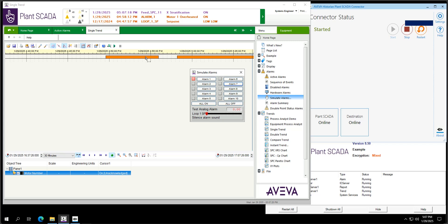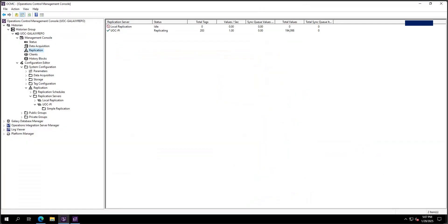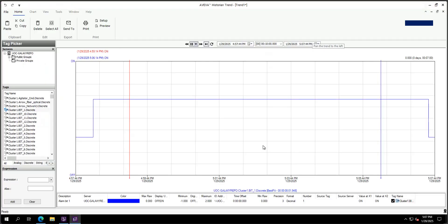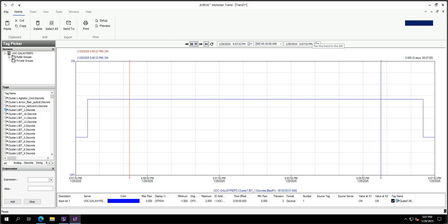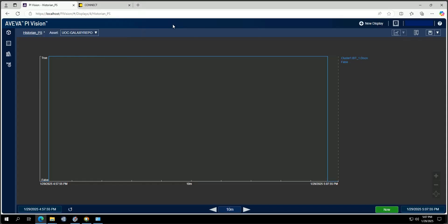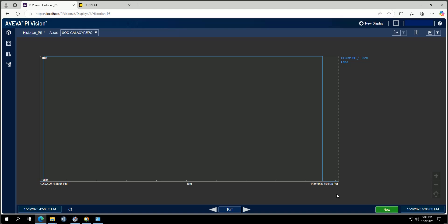If I jump back to my plant SCADA server, I can generate some alarms — those are the tags on my Process Analyst and I can switch off that alarm which I previously triggered. If we go to AVEVA Historian we can see the trend — in the past 10 minutes we can see that tag is off. And if I go back to my PI server, the same value is switched off. The communication between your SCADA, Historian, and PI is now complete — all data is automatically refreshed in PI.